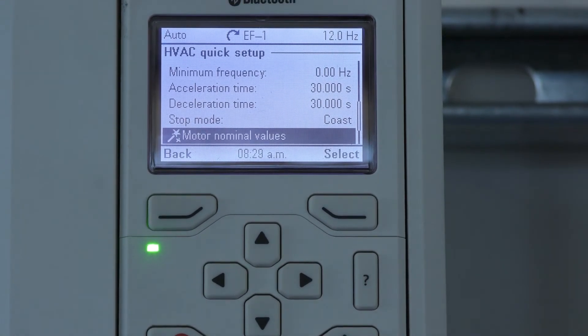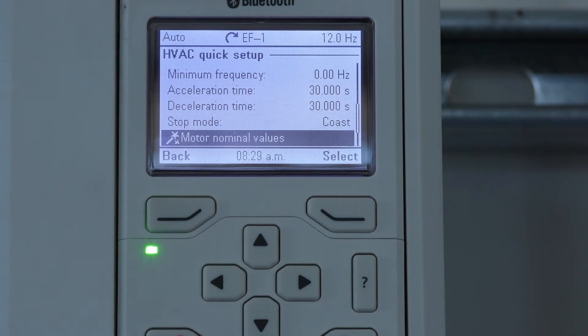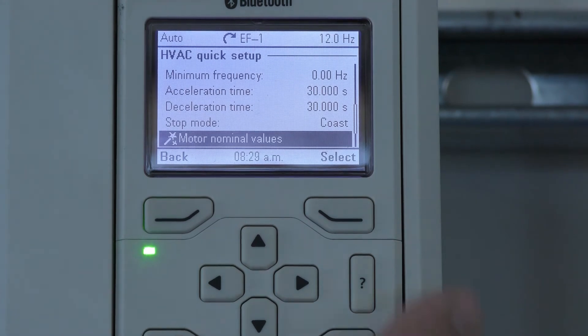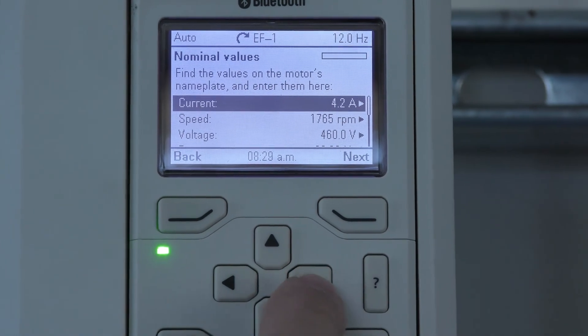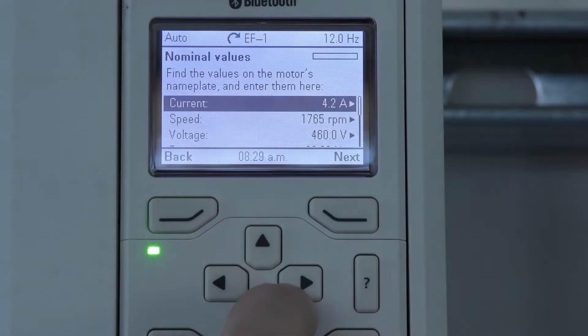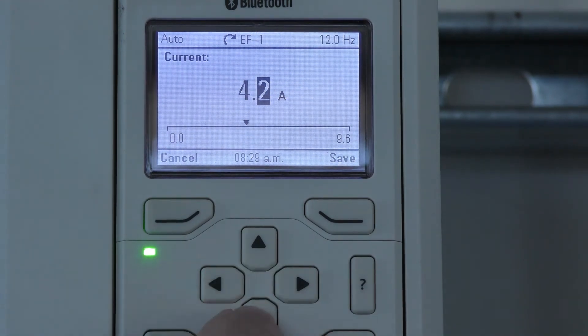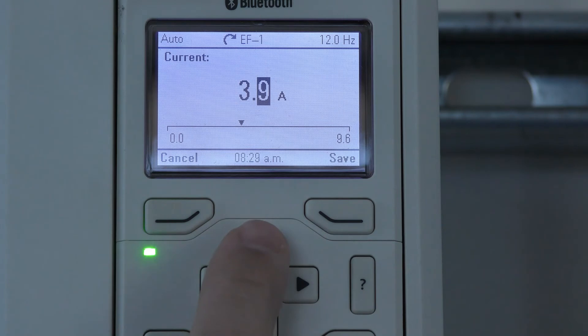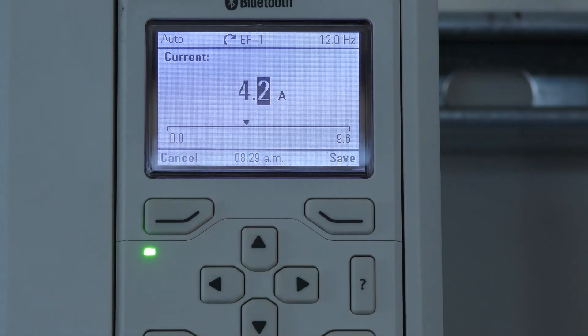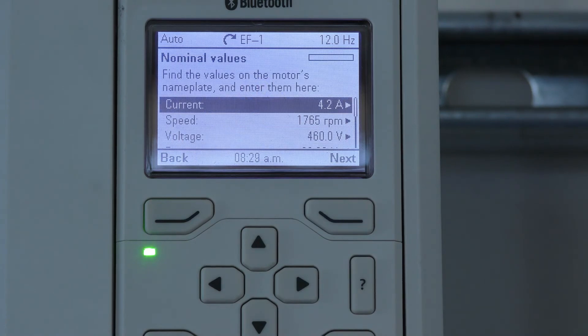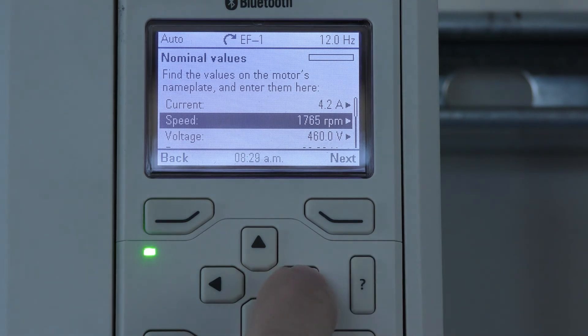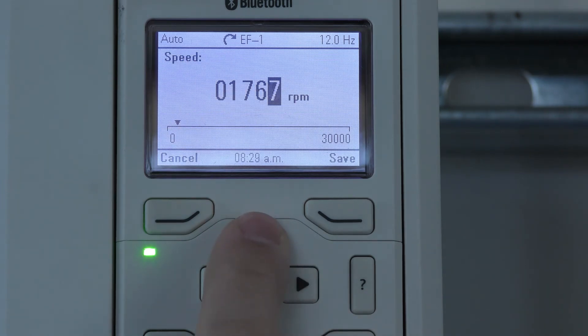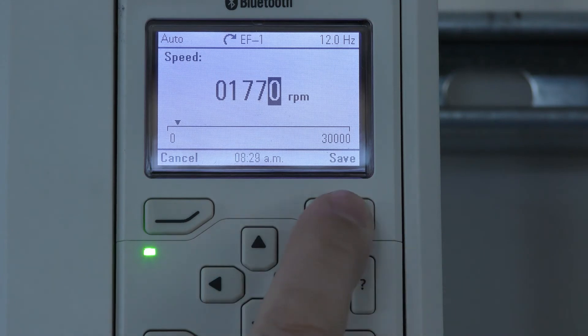Motor Nominal Values is where we will enter the information obtained from the motor nameplate. Select Current and push the right arrow. This is where we can adjust the motor amperage from the motor nameplate. Press Save, then scroll down. Speed is in RPMs and this is where we would adjust the RPMs if necessary, up or down, then Save.